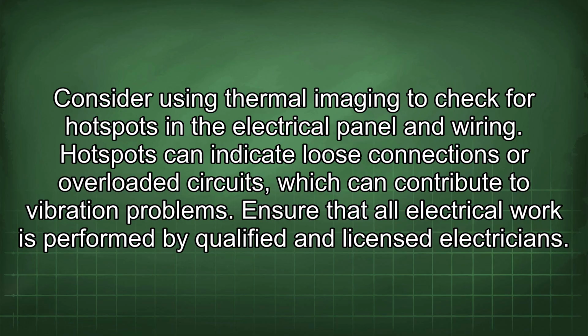Consider using thermal imaging to check for hotspots in the electrical panel and wiring. Hotspots can indicate loose connections or overloaded circuits, which can contribute to vibration problems.